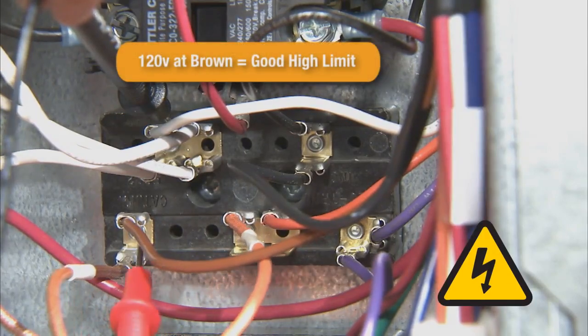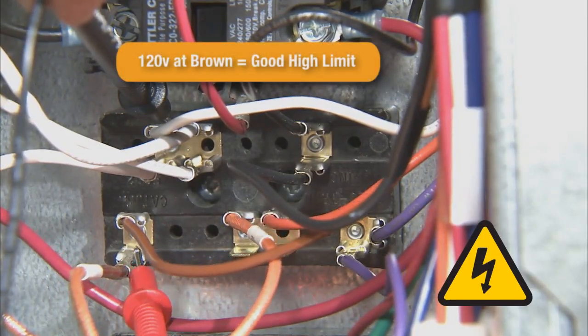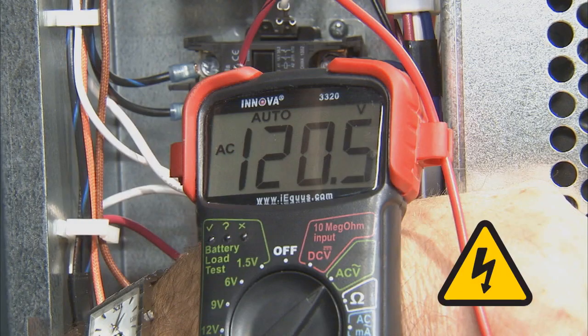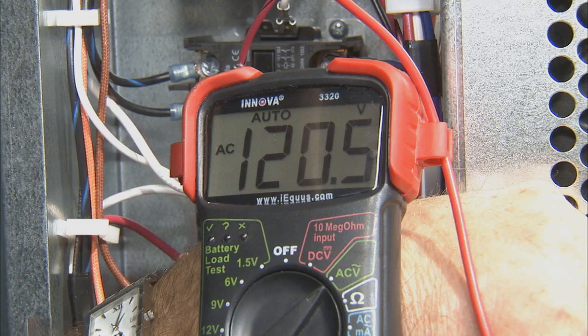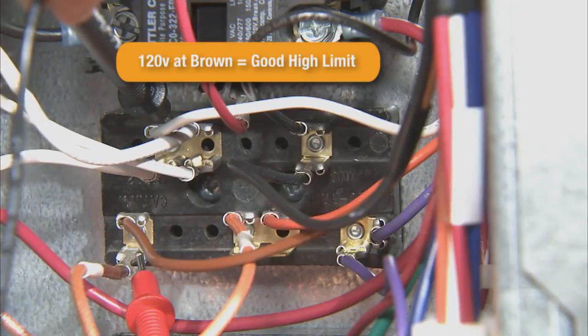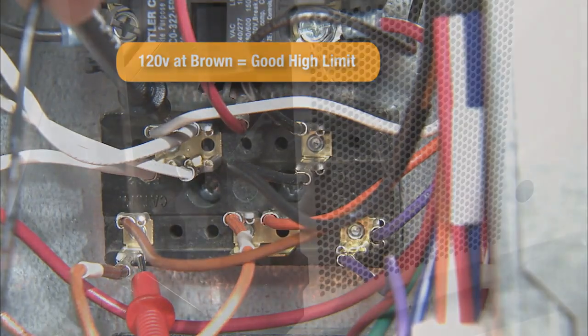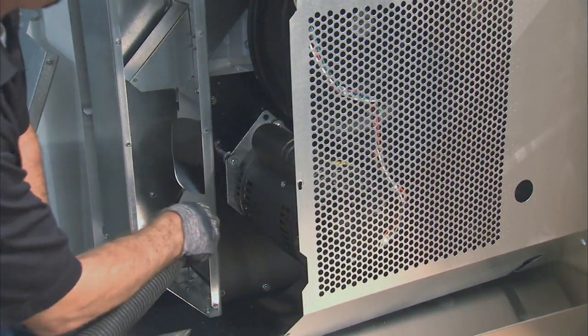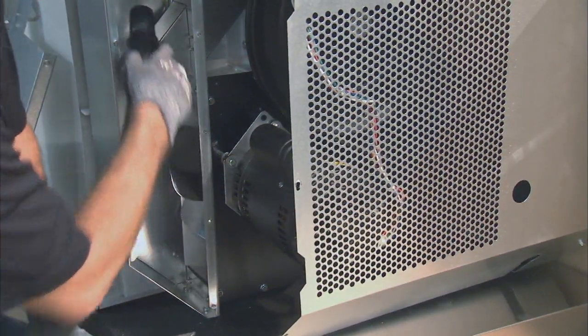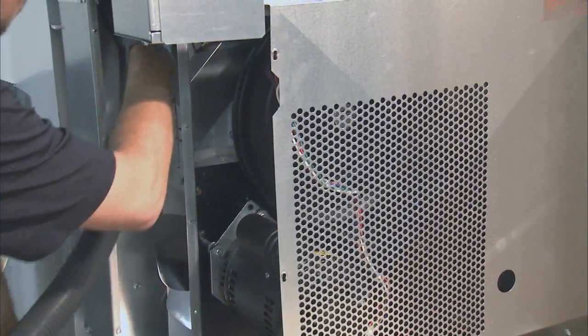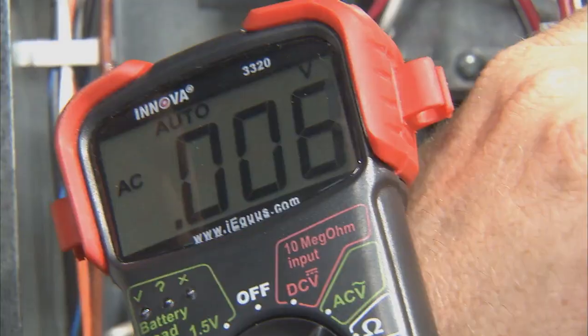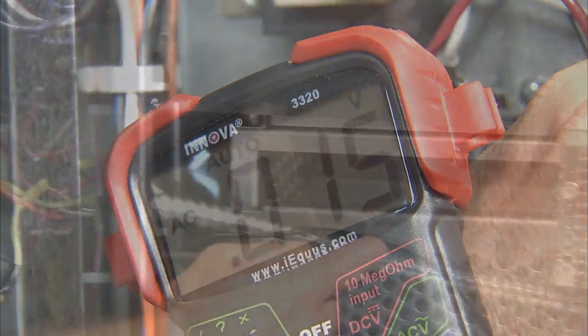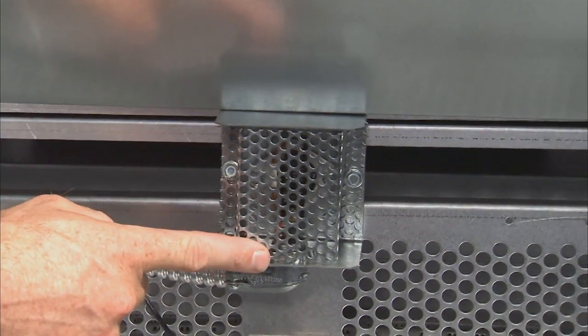Third, test the brown wire connection for 120 volts, indicating that the high limit thermostat on the back of the burner housing is working properly. If voltage is not constant during this test, there is a deficiency with the airflow through the machine and the ductwork needs to be cleaned. The incoming makeup air should be inspected. If the voltage is never present, the high limit thermostat needs to be replaced.